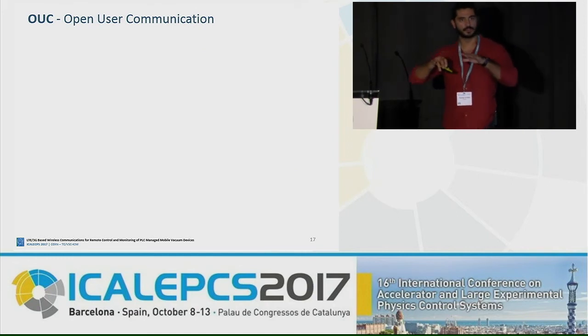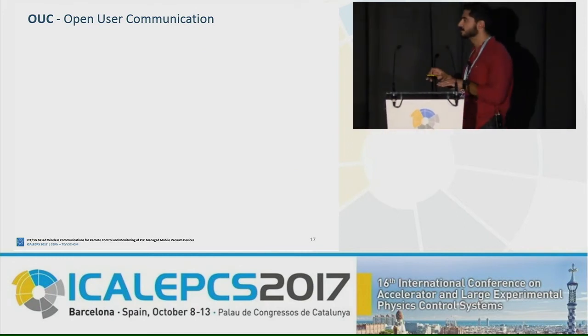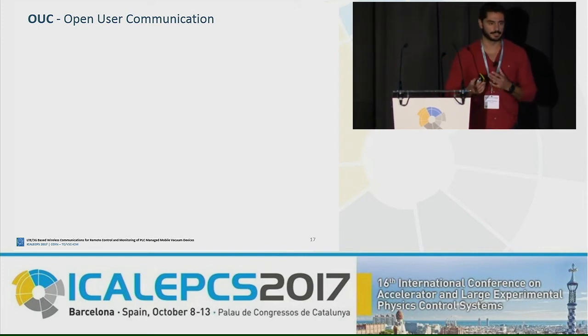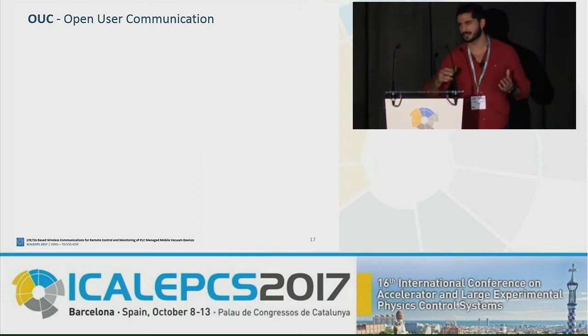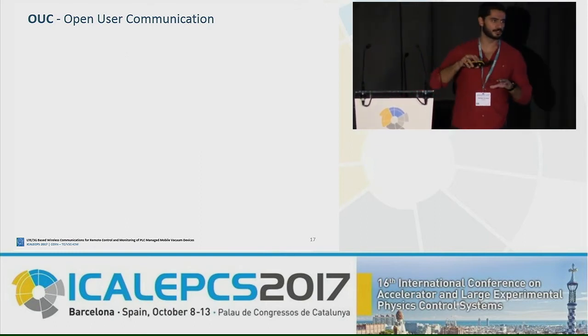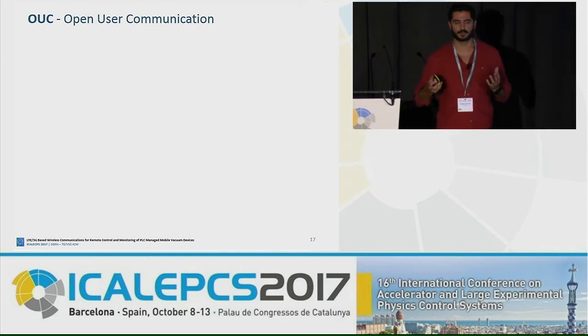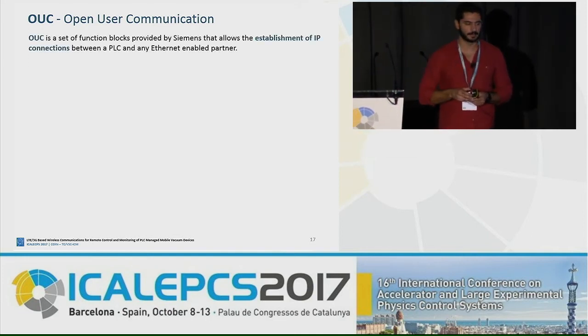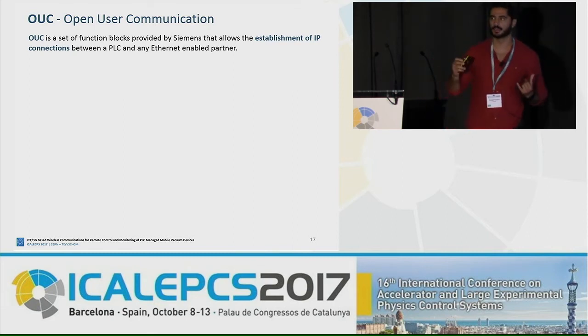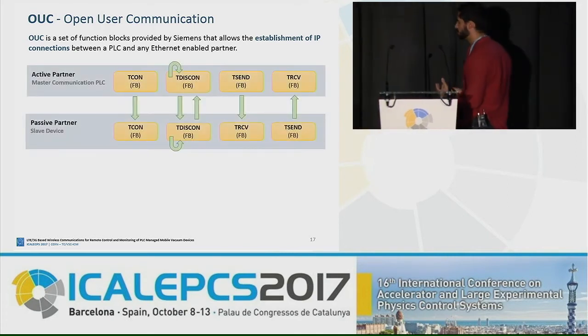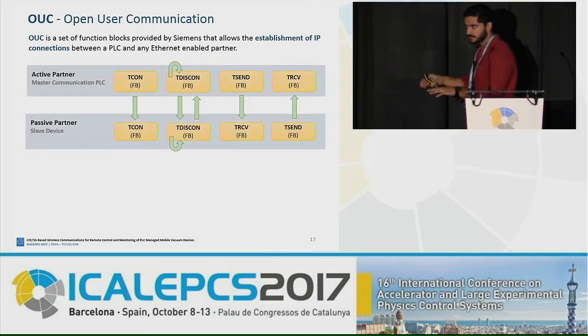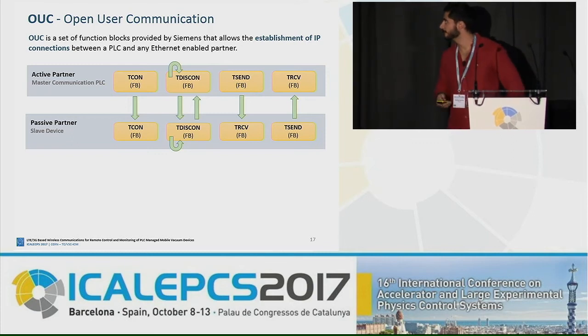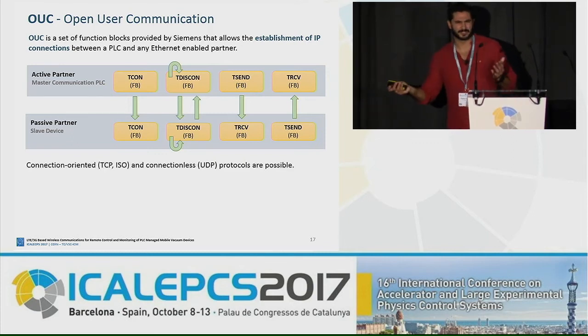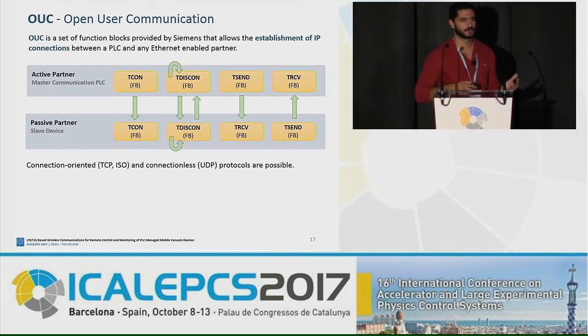Actual communication between each one of the slaves and the master is implemented using open user communication. This is a set of functions that Siemens provides that essentially allows your PLC to speak to any device that supports Ethernet, that has a TCP/IP or UDP protocol implemented. So we can establish IP connections between our PLC and any other thing. Here we are establishing an IP connection between two PLCs, so each one of our slaves and our big master communication thingy. And okay, you can configure this to run TCP, to run UDP, or to run ISO.